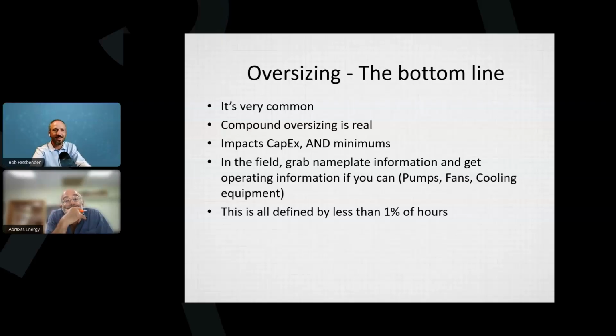I think the biggest thing is taking a look at what you did and not adding a safety factor, and then handing it off to your engineer and having them add a safety factor. Know your assumptions, maybe plot it out. If you have the load, some software does show you the people load, the lighting load, the plug loads, and you get an idea of that. If you add up all the people, some programs tell you how many people are in there. Is it way more people than the building holds? If so, you really don't want to add a safety factor and then hand that off to someone and they size, it depends what you're sizing. Let's say it's fan coil units.